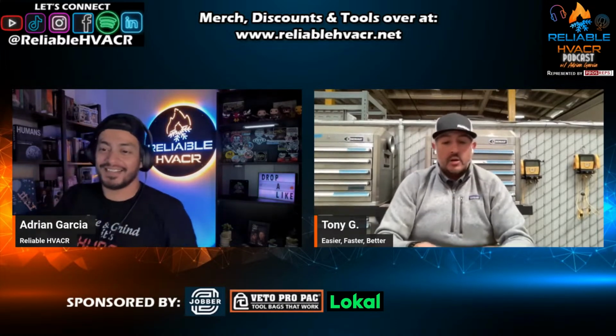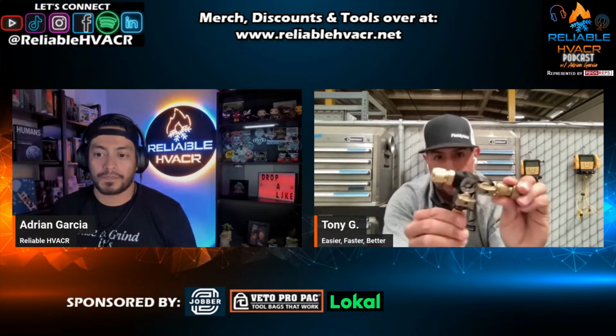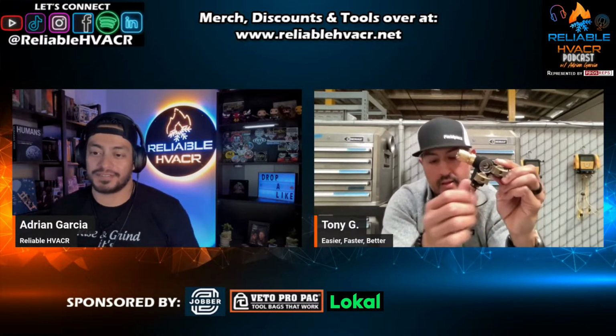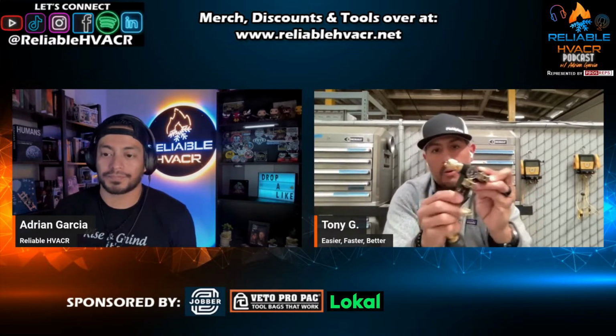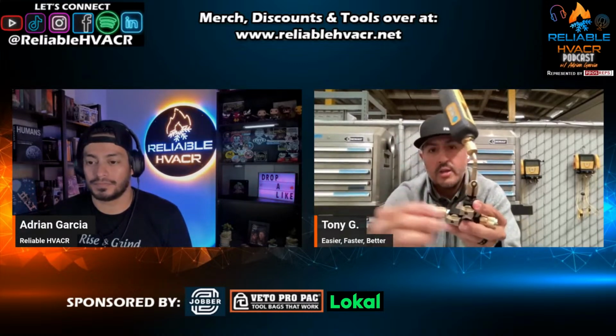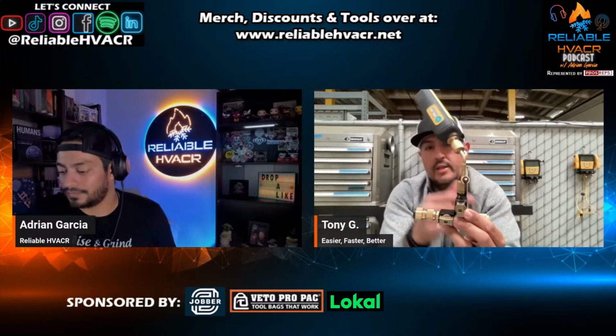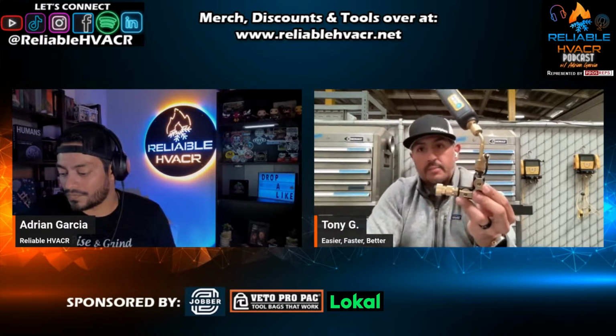Yeah. So we developed on the high end of the Fieldpiece valve core removal tool a second ball valve integrated into this side port right here. Yeah, I cannot wait till those are out. Yes. So now when you screw on your micron gauge onto the side port of your system, you can pull your vacuum, and then when you're done pulling your vacuum, you can just blank this off. And now this is completely isolated, and you charge the system back up with refrigerant. You don't let air back into your setup, and you don't expose your micron gauge to positive pressure.